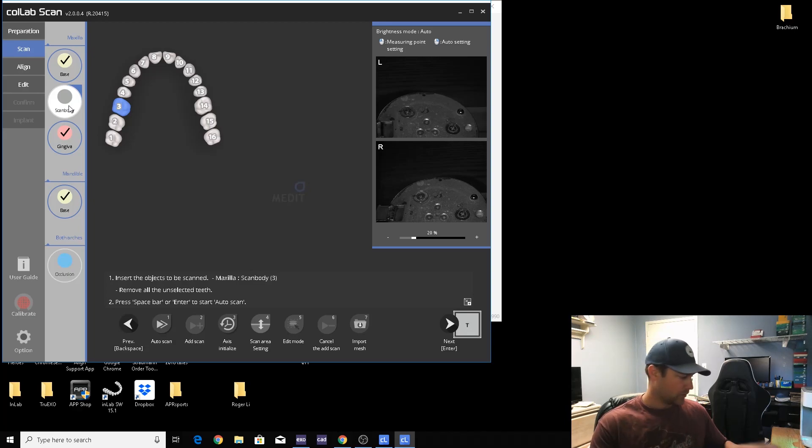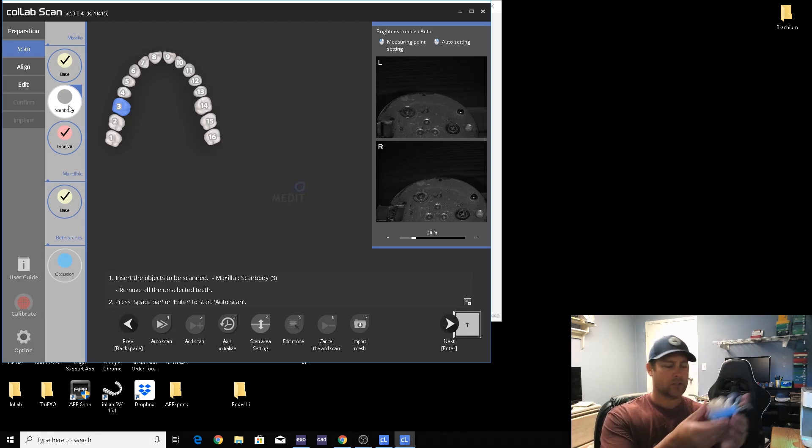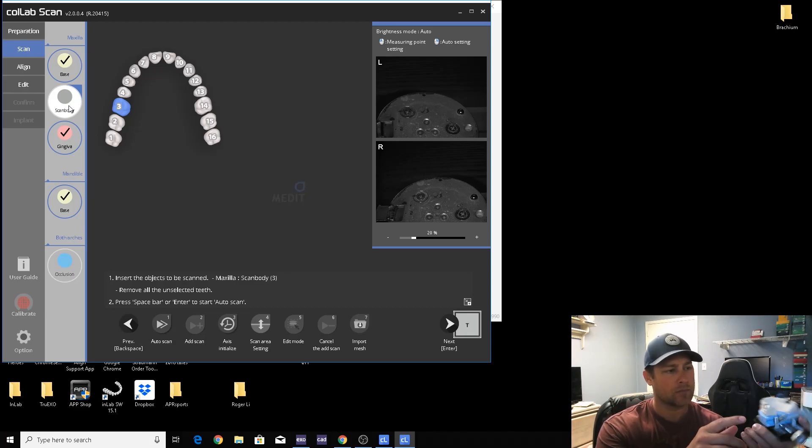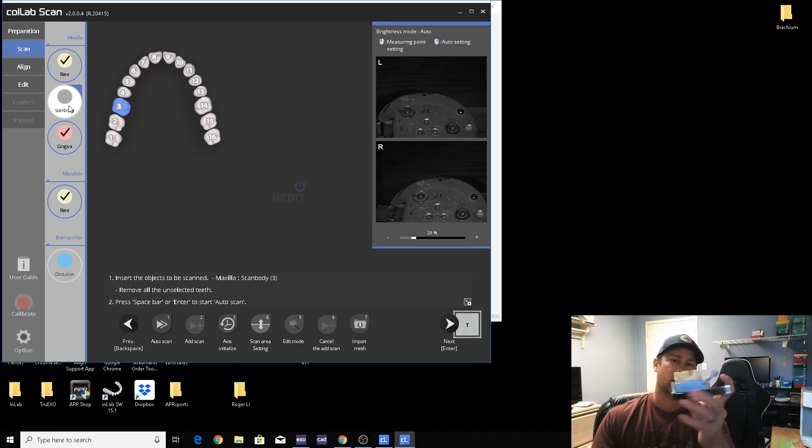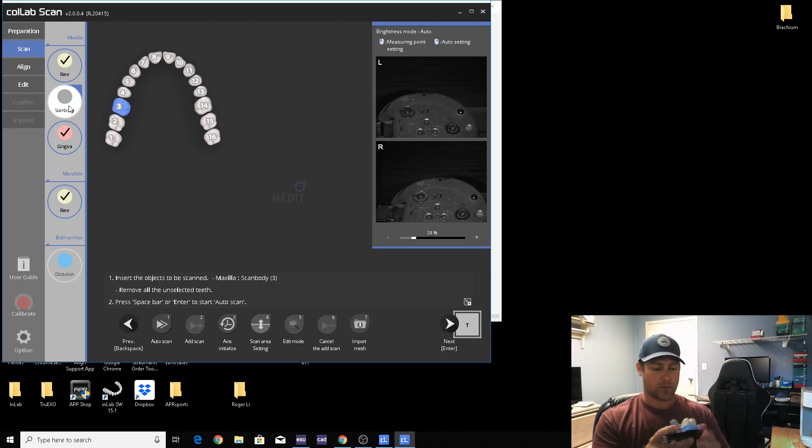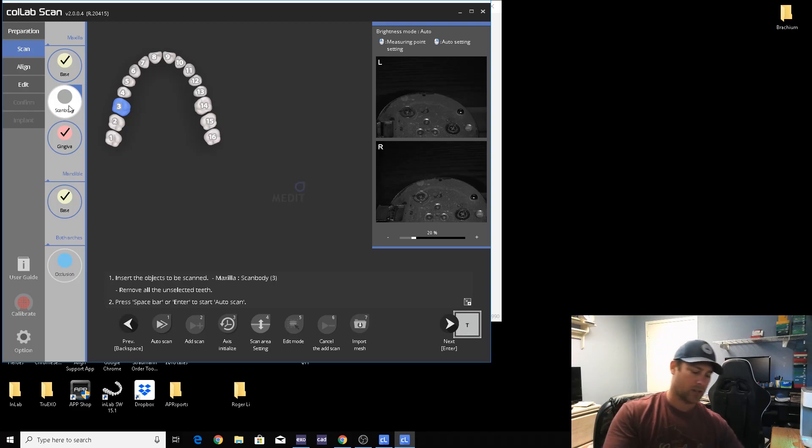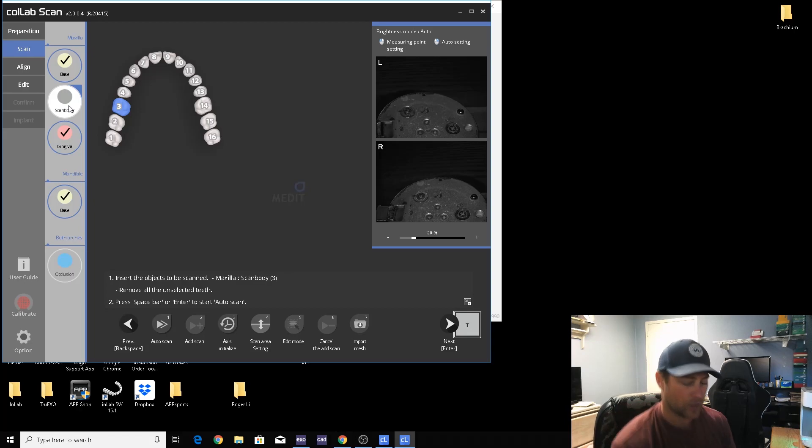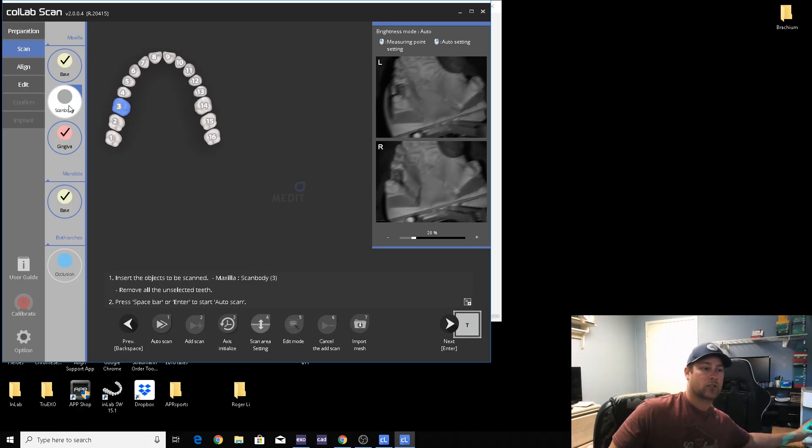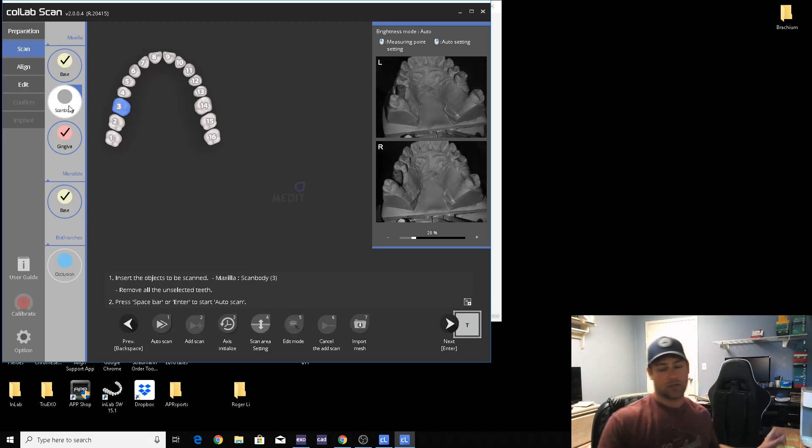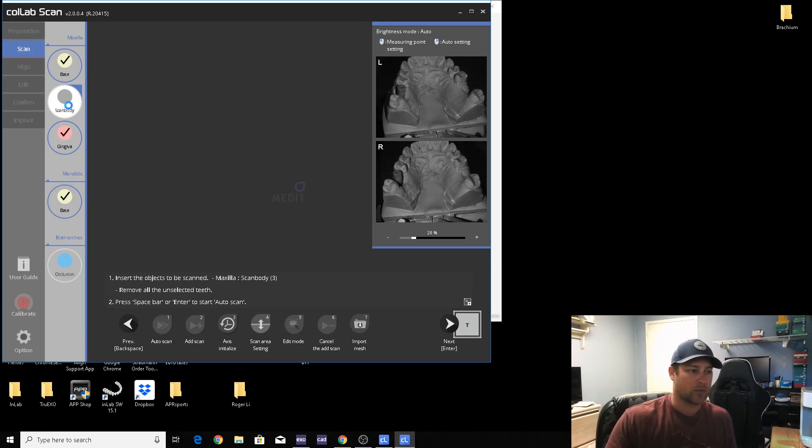If you can help it, and this isn't an ideal situation, but try to get the flat sides coming out of the buccal side as best you can, or lingual side. You don't want the flat sides to be in the proximal area. It's tougher for the scanner to pick it up, and those are the most important sides, are the flat sides, so that you can orientate the scan body properly in the software.